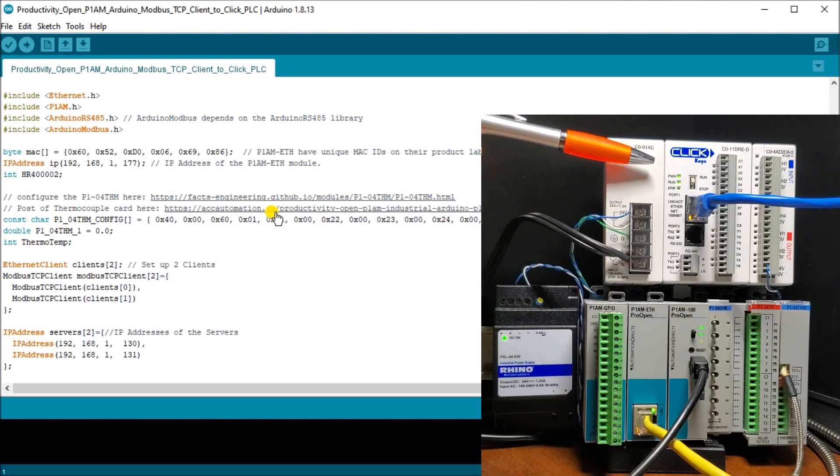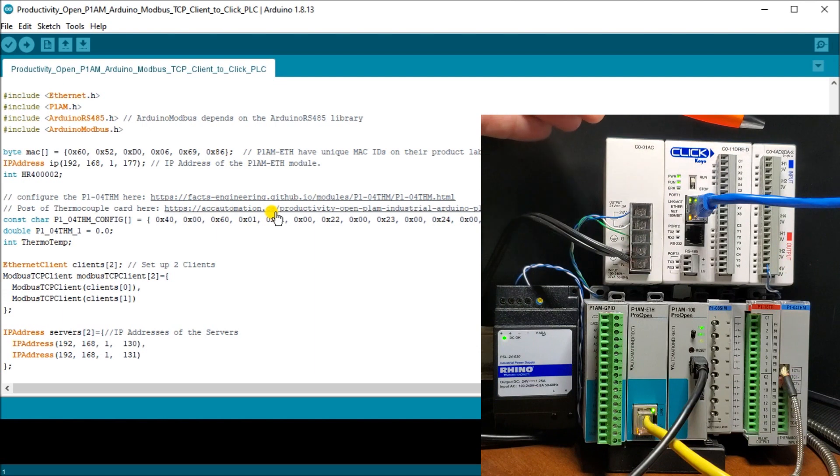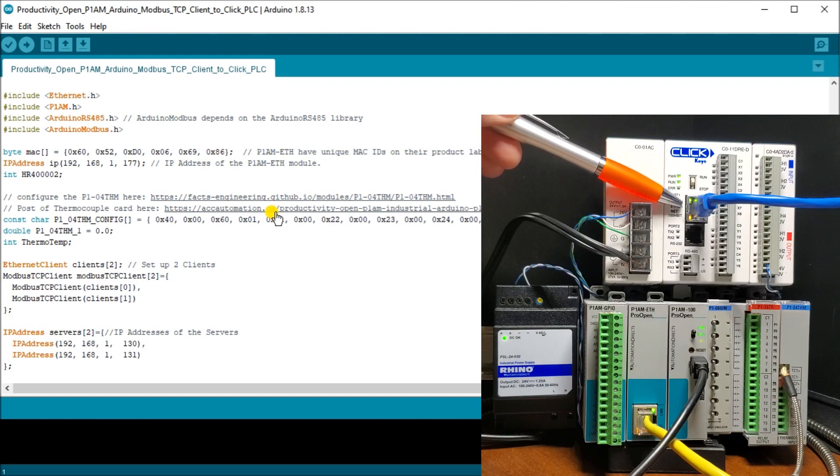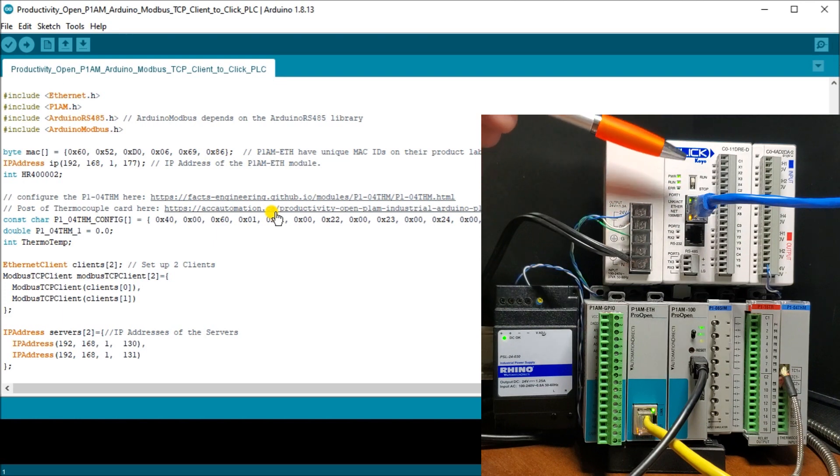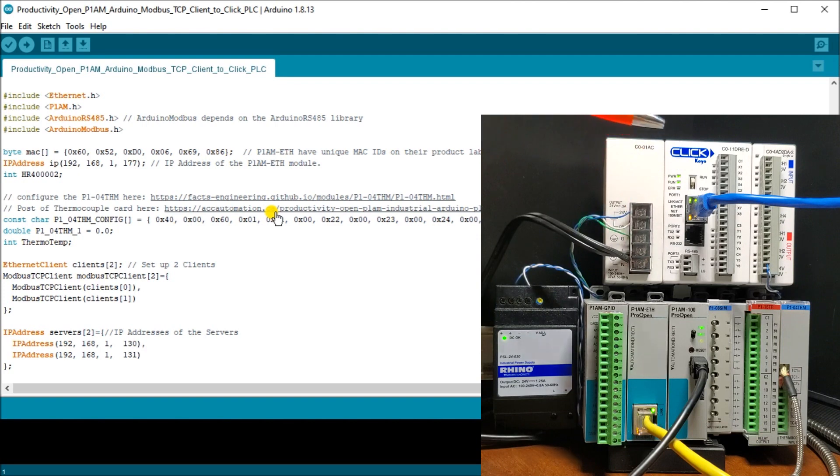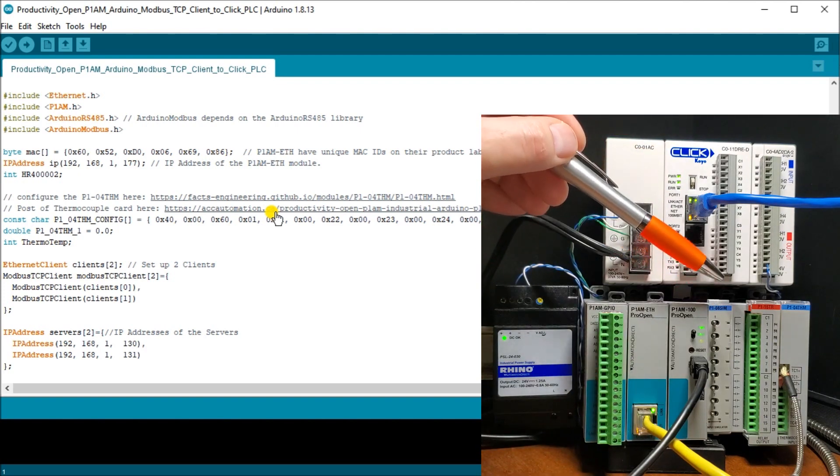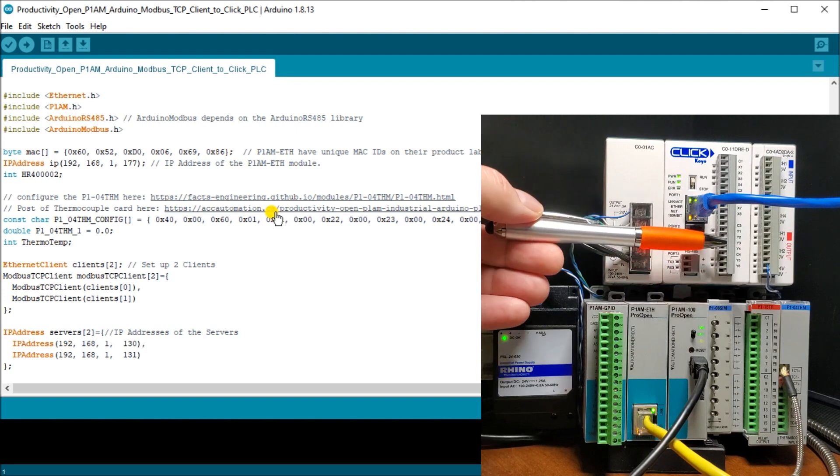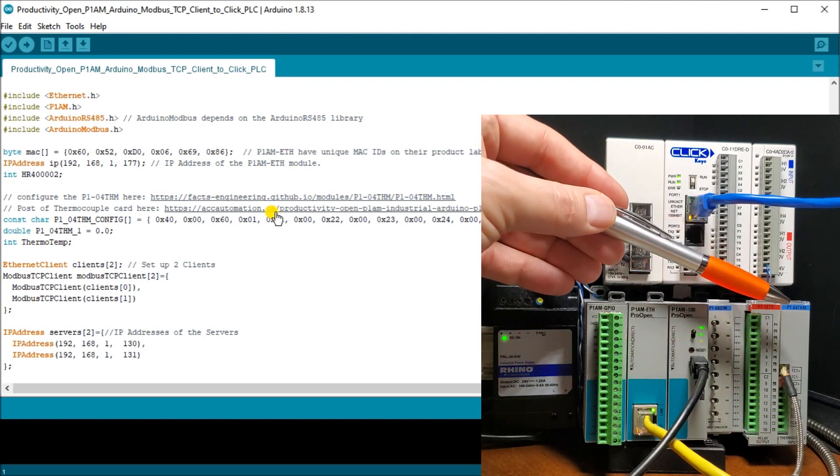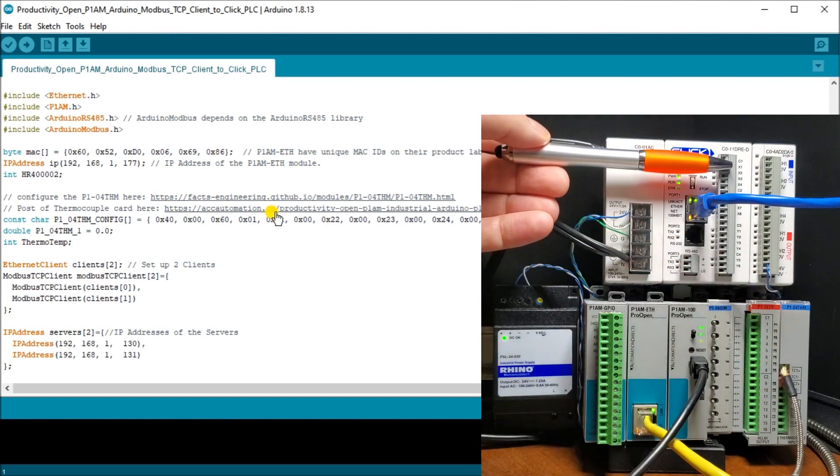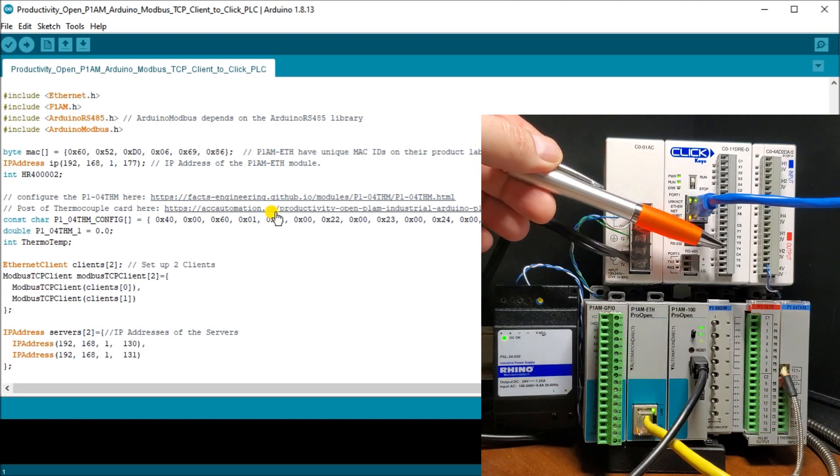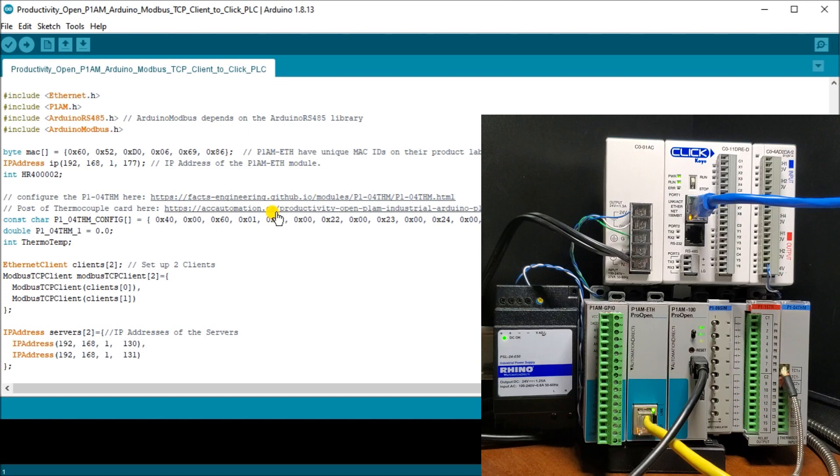Then we have up here, we have a Click. It's the C0-11DRE-D. So our power supply is on the left hand side. Then we just have an analog card here. But we will not be using that analog card. Now with this model we have an Ethernet port which is doing our Modbus TCP communication. And that's the port that we just set up using the software. So what we're going to do is take the simulator inputs and we're going to, as they turn on, turn on the corresponding output of our Click PLC. And we're going to take our thermocouple input here and we're going to put it into an internal register here in the PLC. Then what we're going to do is ensure that we have communications. And when we don't, we will reset these bits here so that our program can tell or determine whether or not we have good communications.